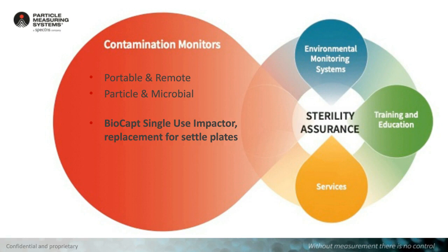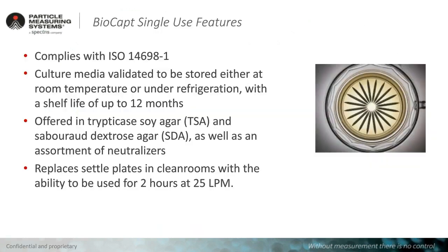The BioCapt single-use complies with ISO 14698 Part 1. The culture media is validated to be stored at either room temperature or under refrigeration with a shelf life of up to 12 months. We offer this in TSA and SDA, and we offer a variety of neutralizers. These can replace settle plates in clean rooms with the ability to be used for up to 2 hours at 25 liters per minute.